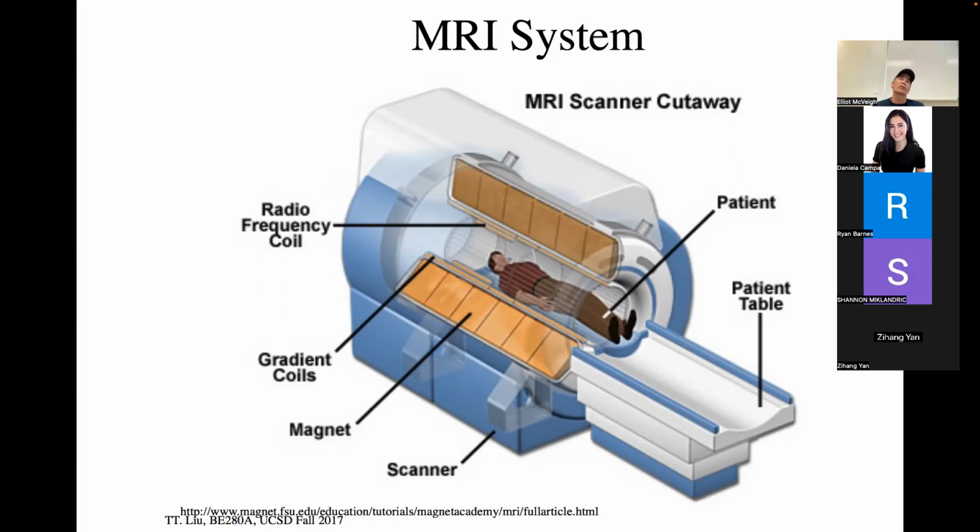So when you walk in the room, or if somebody else who is unaware of that walks in the room, if they have any metallic ferromagnetic devices on, like their ID badge, their eyelets in their shoes, an X-Acto knife, something like that, that device, when you get it close to the magnet, will just fly into the magnet at a high velocity.